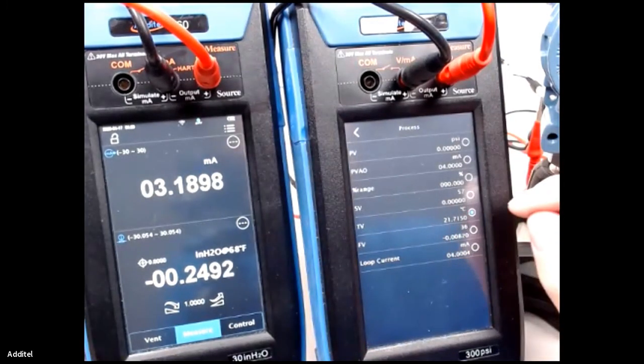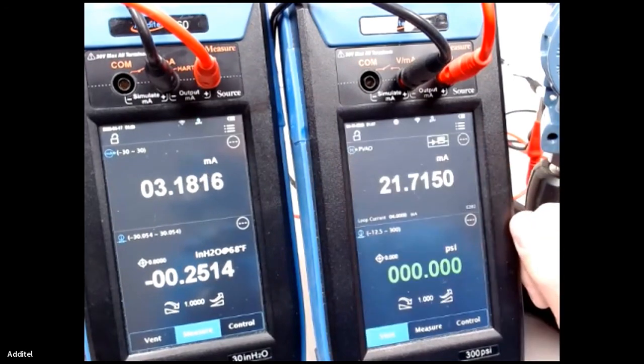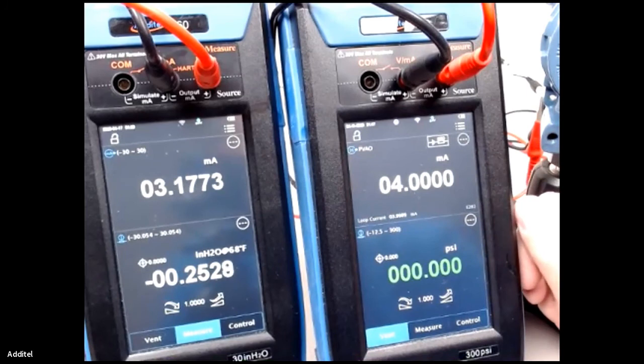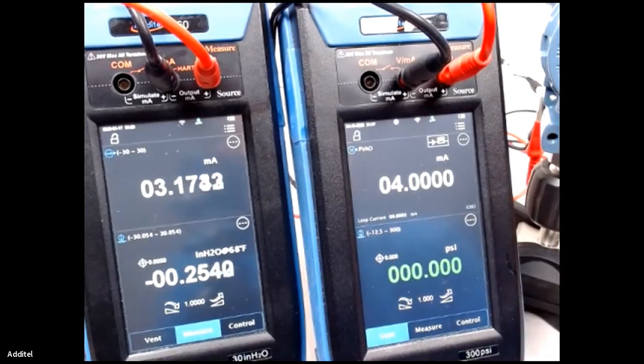So if we want to read milliamps, pressure, whatever we want to read, we can. I'm going to go ahead and select milliamps so we can see the milliamps. This is obviously a 4 to 20 milliamp transmitter. We're at 0 and we're reading pretty much exactly 4 milliamps, as you can see there on the screen.